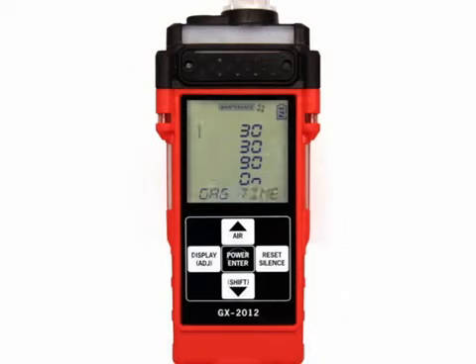To update the gas time setting, with the cursor next to the gas time and with gas time displayed along the bottom of the screen, press Power Enter. The factory setting is 30 seconds. The value will begin to flash. Use the Air or Shift buttons to select a new gas time. The gas time is the amount of time that the instrument is exposed to gas during a bump test. The time increments are 30, 40, 60, and 90 seconds. Once a value is selected, press and release the Power Enter button to save it. The value will stop blinking.